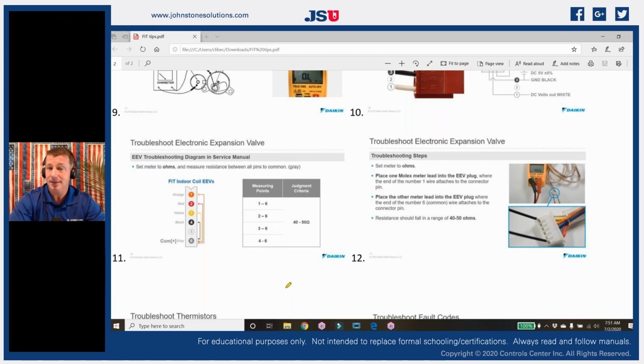Almost all Daikin pieces of equipment that have an EEV, whether it's a unitary, a commercial, or a mini split, it's the same principle. We are going to have 4 coils inside of that one little head. And if you've ever installed any type of electronic expansion valve, when you first power them up, you're going to hear it.